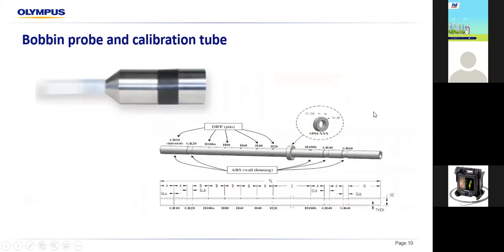So this would be the probe and the calibration tube that you will be using. You have your bobbin probe, of course, for your ECT. And for your calibration tube, as I mentioned a while ago, if you're using our calibration tube, you have three additional defects here. You have your big hole, which is bigger in diameter compared to the hole on the ASME standard. And then you have your OD groove of 40% and your OD groove of 60%. For ASME you only have one, which is the OD groove of 20% here.